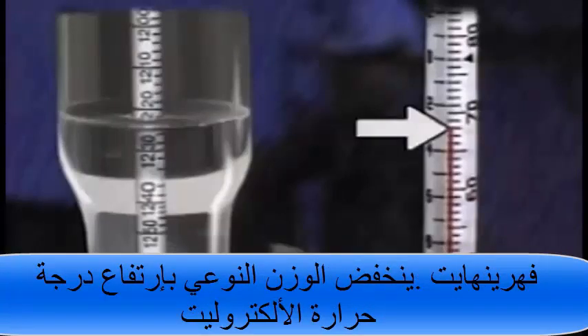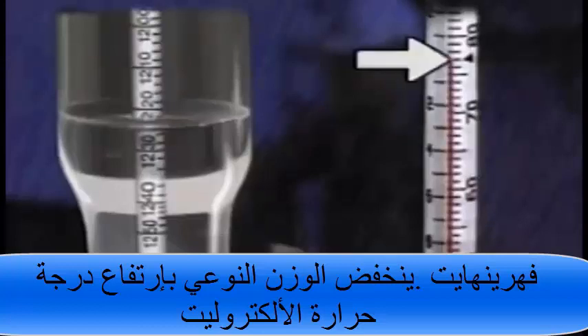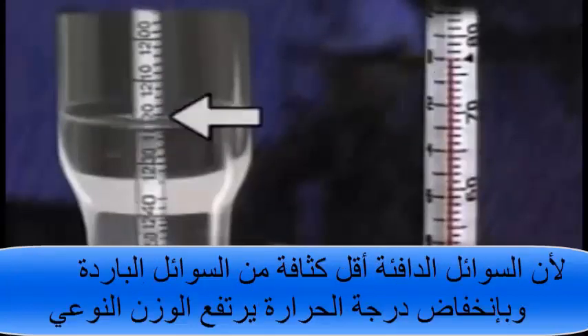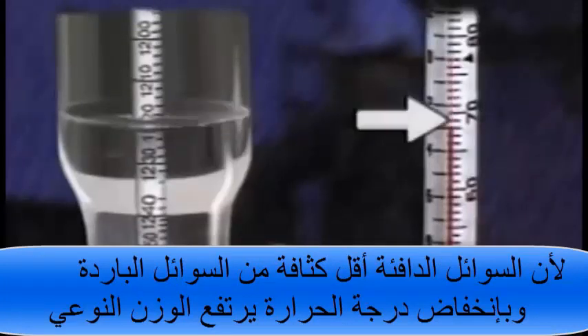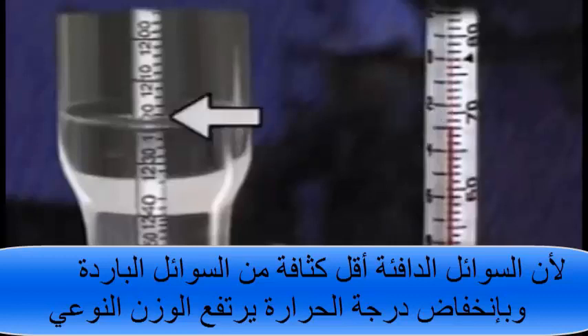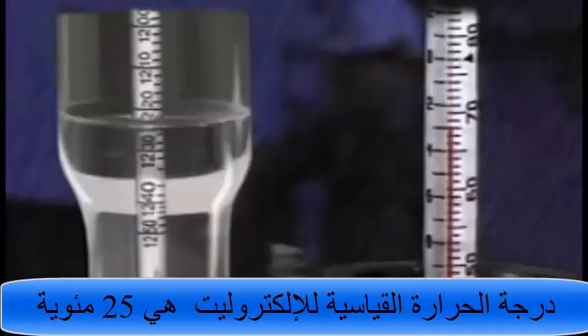When electrolyte temperature increases, its specific gravity decreases, because warmer liquids are less dense than cooler liquids. When the temperature decreases, the specific gravity increases. The normal or standard reference temperature for electrolyte is 77 degrees Fahrenheit or 25 degrees Celsius.